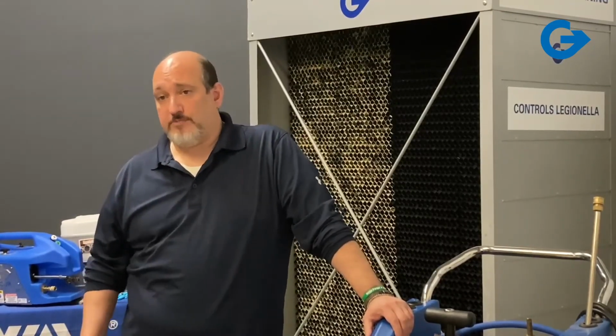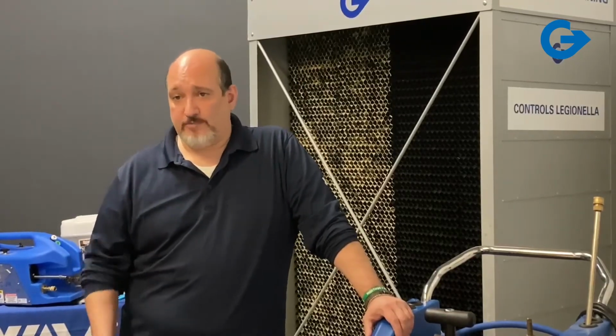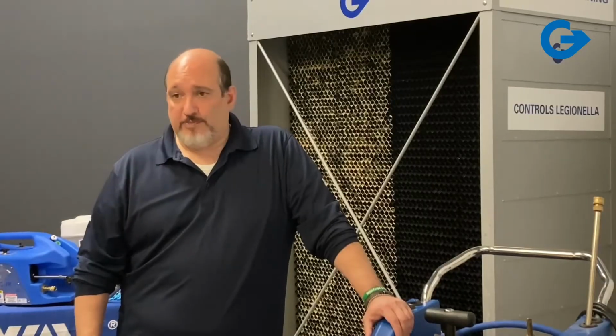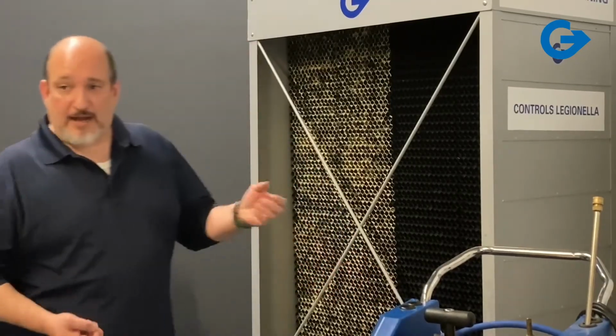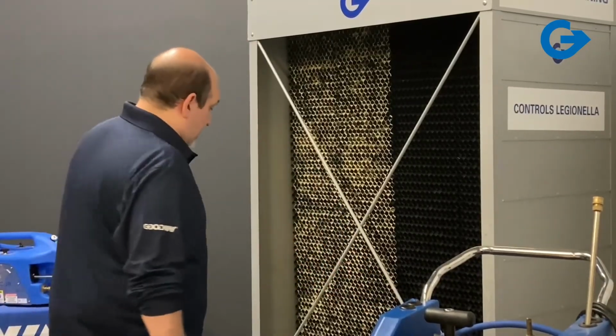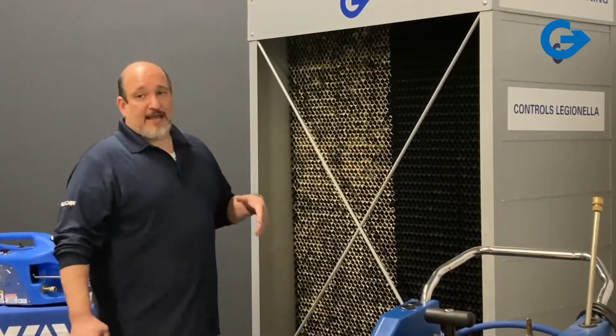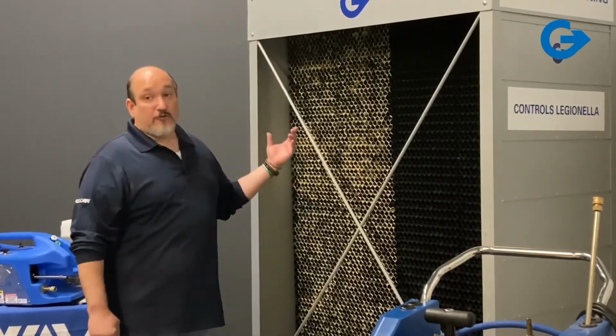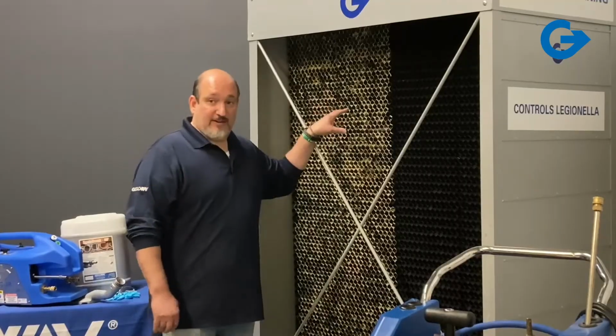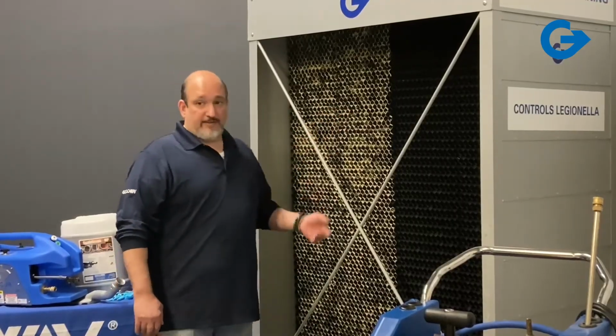It's putting out 3 GPM, but the pressure on it is scaled down to only 300 PSI. And that 300 PSI is enough to help break the bond of the scale to the fill, and that GPM helps flush it out really thoroughly and get deep penetration into the fill and do your rinse down.